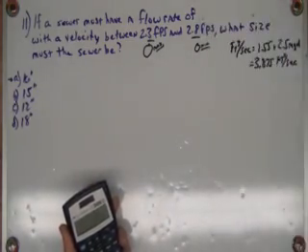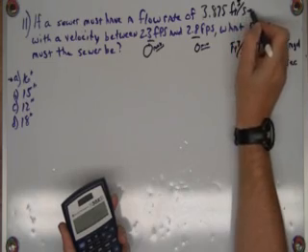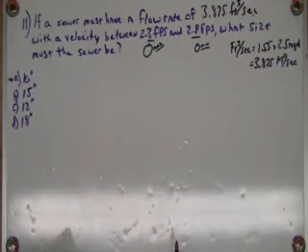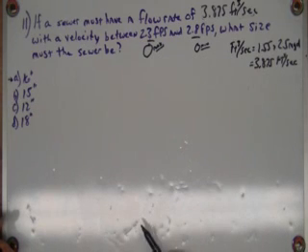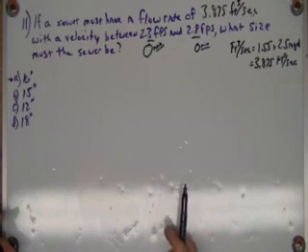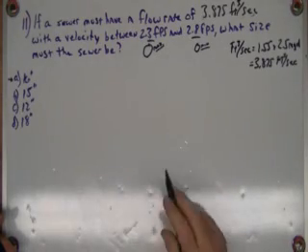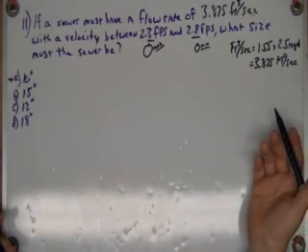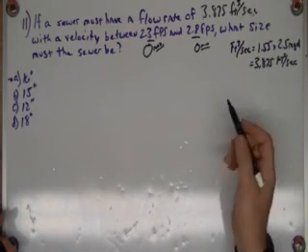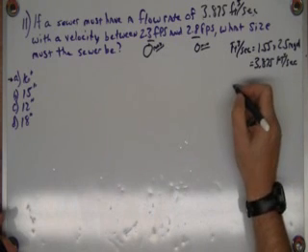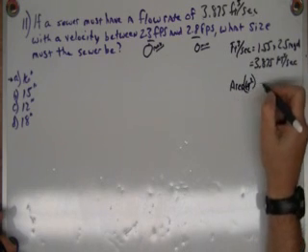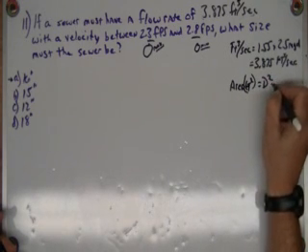So the problem now reads: a sewer must have a flow rate of 3.875 cubic feet per second with a velocity between 2.3 and 2.8 feet per second. I'm going to start with the maximum velocity of 2.8 feet per second for the minimum pipe size. I need the area formula: Area (ft²) = diameter² × 0.785.